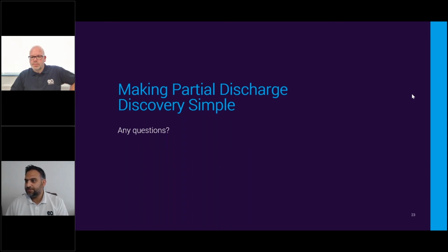There was one more question, about Ultra-TEV activity or PD activity on cable terminations. You can detect PD activity on the cables or the cable terminations just by using, for example, the Ultra-TEV Plus 2 instrument. Not typically, though. When you're looking for cable PD, you use a high frequency current transformer, HFCT. You clip it around the earth to capture the PD. With that, you're looking at the PD along the length of the cable.